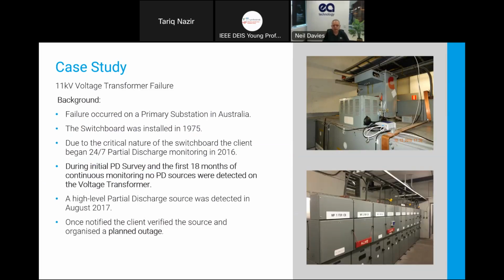Okay, let's look at case study 2. This is on an 11 kV voltage transformer that we say failed. It didn't actually fail. The failure was prevented. So the functional failure occurred. The switchboard would have been installed circa 1975. Due to its criticality, I've got permanent monitoring on there since 2016.